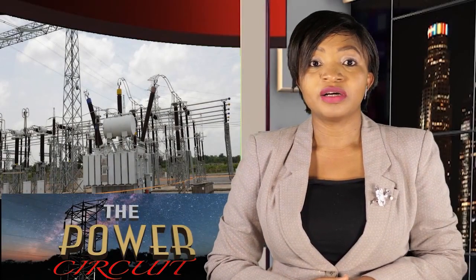Have you heard of power transformer regeneration maintenance? Well, it is a routine exercise by the Transmission Company of Nigeria, TCN, to replace contaminated oil in some existing transformers to optimize their operational capacities. There was a practical execution of this activity at the 330-132 kV Osogbo substation in Osun State. And the Power Circuit tells you the exciting story.